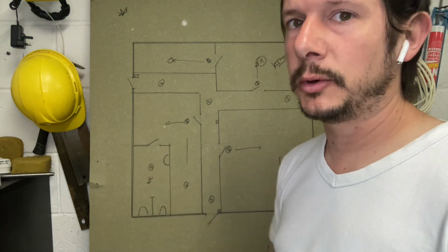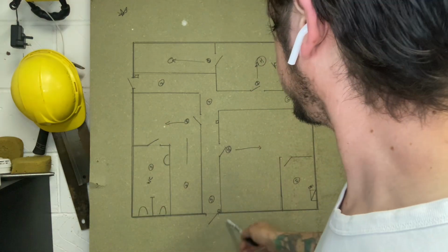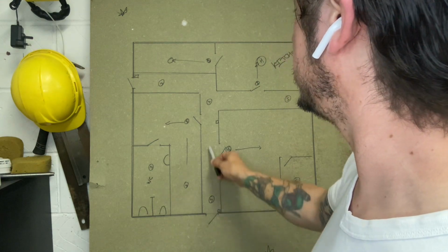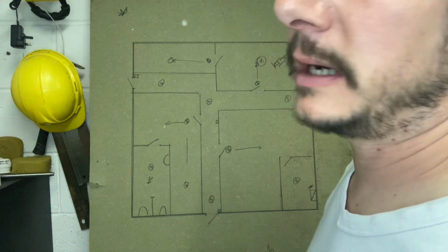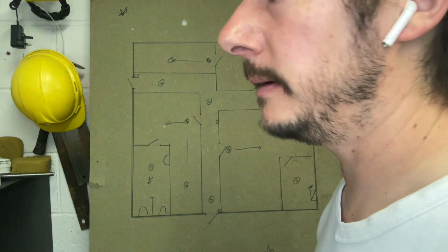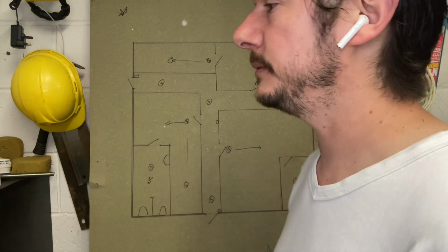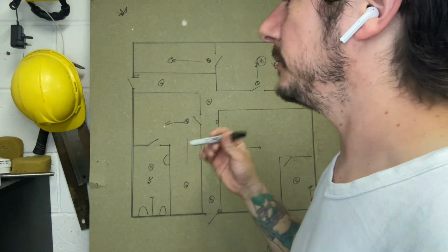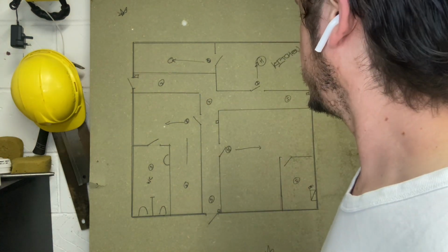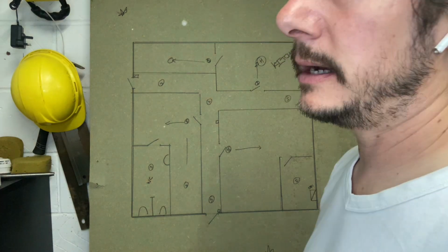So someone's hit a call point, from here, can you find, on the zone you're in, can you get to the fire within 45 meters? Can you see it visually if you've got to run around? So then you might start throwing more in. I mean, that's kind of getting into the realms of analog addressable really, but there you go.